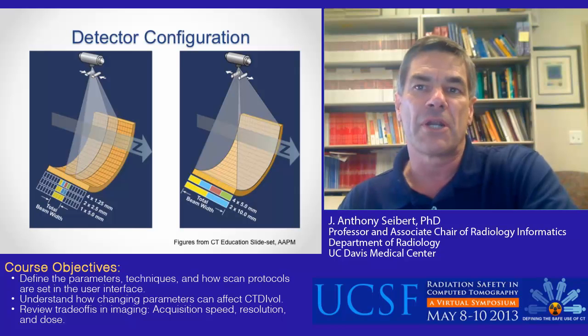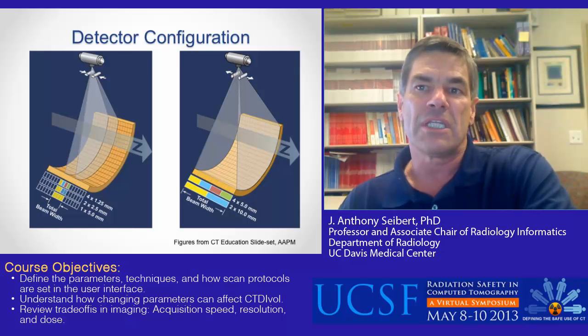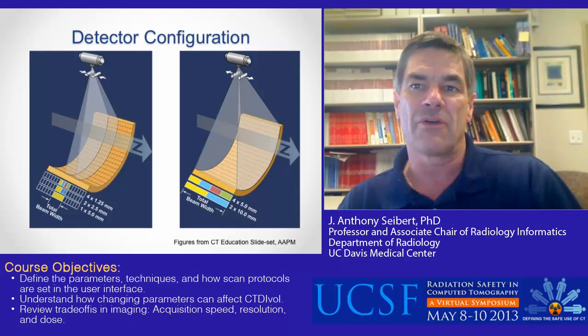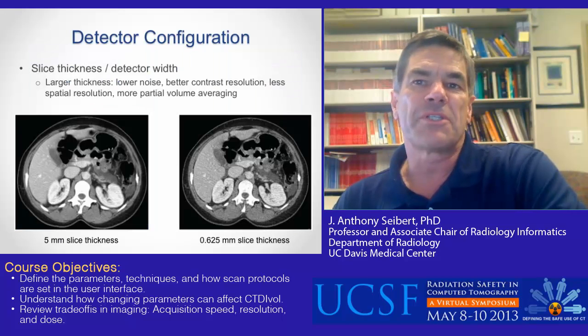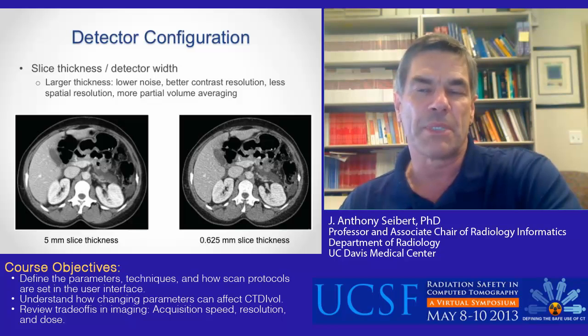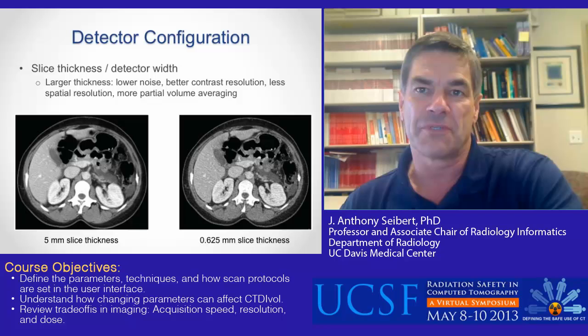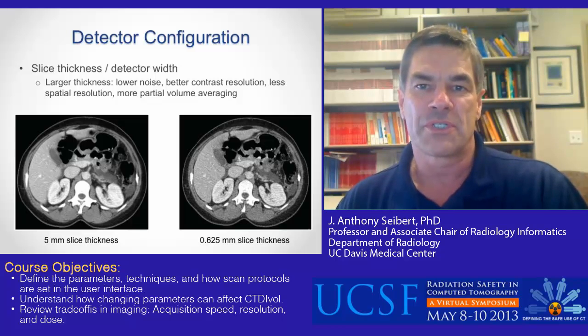This slide illustrates a comparison of a narrow total beam width of 5 mm on the left and a wide total beam width of 20 mm on the right. Since the penumbra width is the same in both cases, the efficiency of the narrow beam width setting is less, so the CTDI vol would be higher. However, in terms of radiation scatter and associated contrast resolution, an image would likely present with better contrast resolution with the narrow beam width. The number of x-rays incident on a given voxel is inversely proportional to the slice thickness. By selecting a large slice thickness, the relative noise in the image will be less, and contrast and contrast noise of large objects is improved. However, small details are averaged within the voxel, and spatial resolution will be lost. In this abdominal CT example, to get the same relative noise values would require 8 times more radiation dose with the thin 0.625 mm slice.